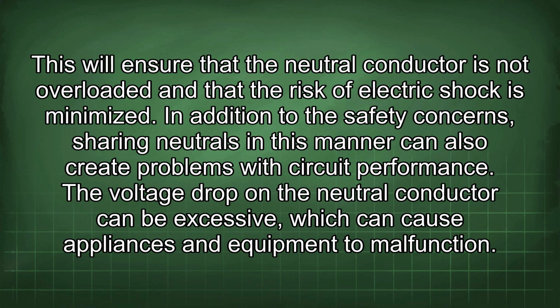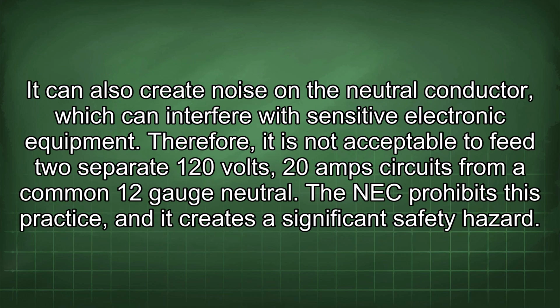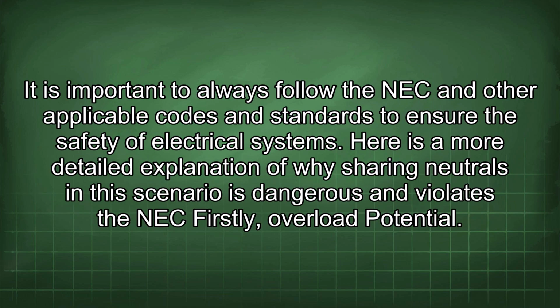In addition to the safety concerns, sharing neutrals in this manner can also create problems with circuit performance. The voltage drop on the neutral conductor can be excessive, which can cause appliances and equipment to malfunction. It can also create noise on the neutral conductor, which can interfere with sensitive electronic equipment. Therefore, it is not acceptable to feed two separate 120 volt, 20 amp circuits from a common 12-gauge neutral. The NEC prohibits this practice, and it creates a significant safety hazard. It is important to always follow the NEC and other applicable codes and standards to ensure the safety of electrical systems.